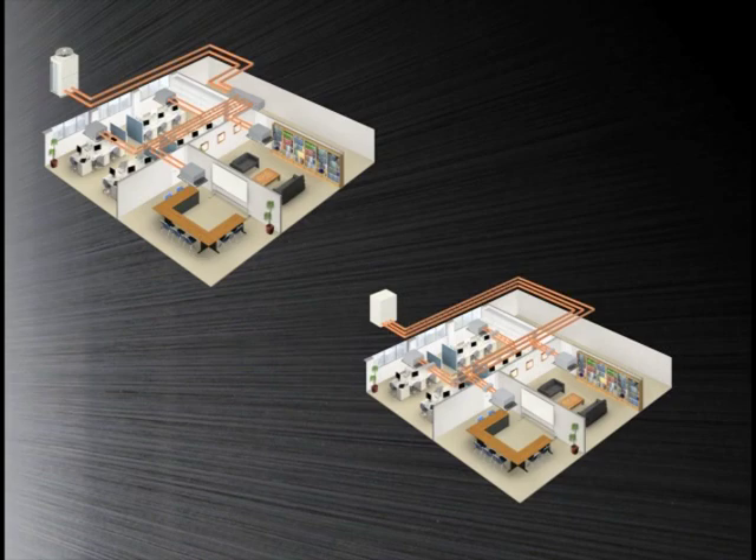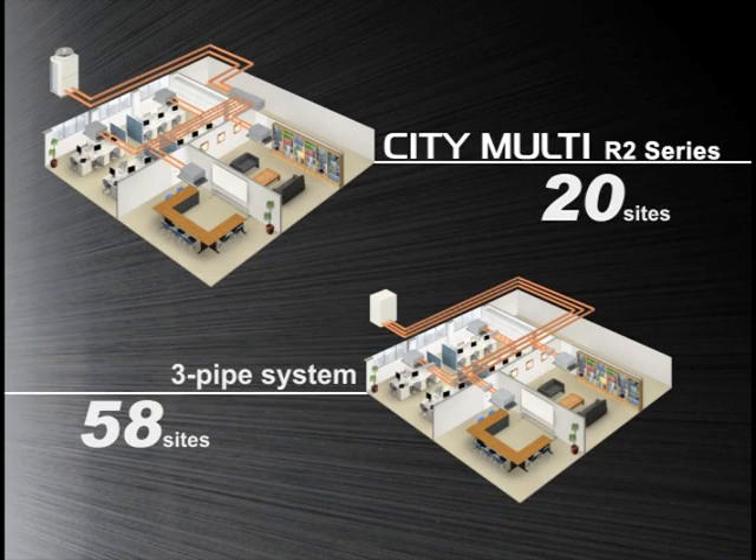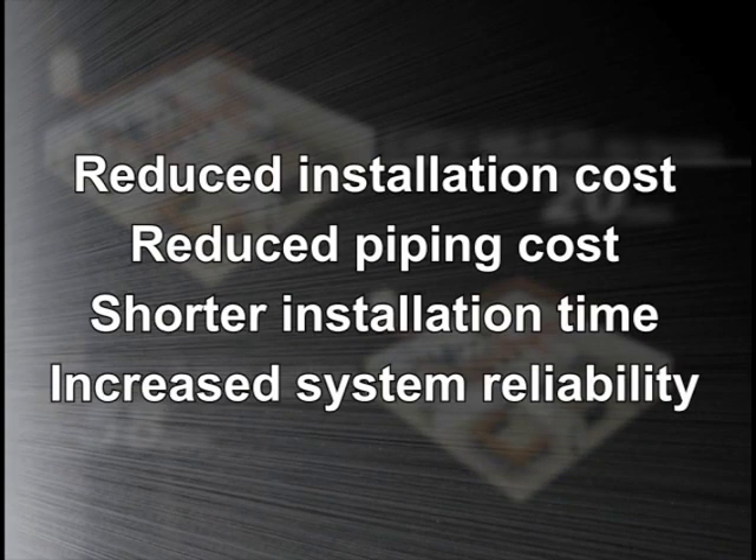Imagine a system with an outdoor unit with four indoor units connected. The City Multi R2 system would require only 20 piping connection sites, as opposed to a three-pipe system, which would require 58 piping connection sites. Our R2 system not only significantly reduces the number of piping connection sites and piping cost, but also shortens installation time and further increases system reliability.